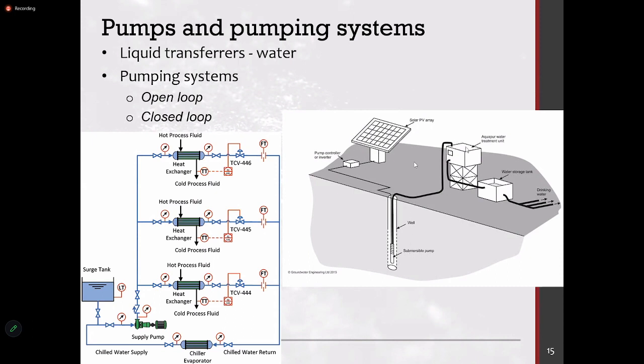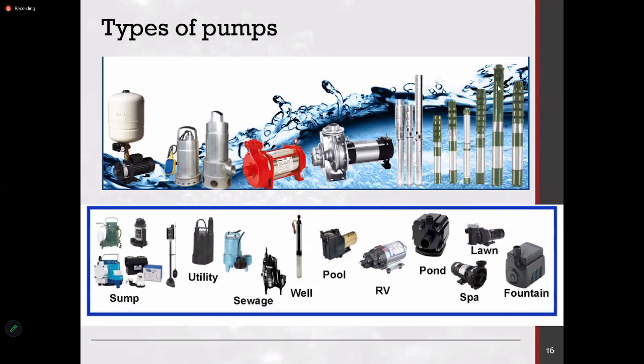But in an open loop system, the height of the tank and how low your well or sump is will all add up to the head, and that entire thing will have to be provided from the pump. So pumps also you will see in different shapes and different constructions. These are mostly booster pumps, submersible pumps where you can put them inside water and operate, overhead pumps, then this type of tube well pumps. So they are in various shapes and technologies. Okay.